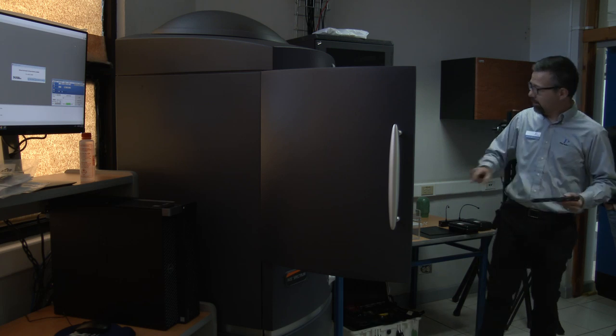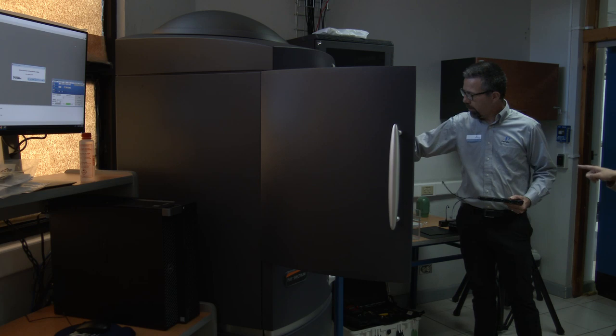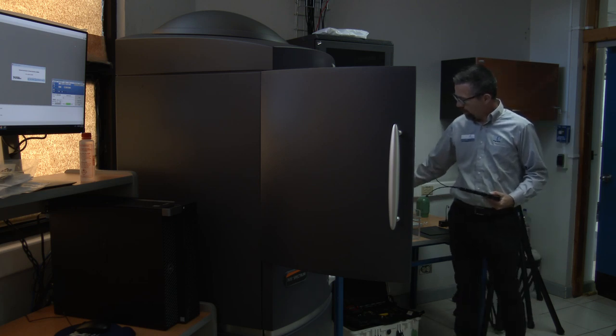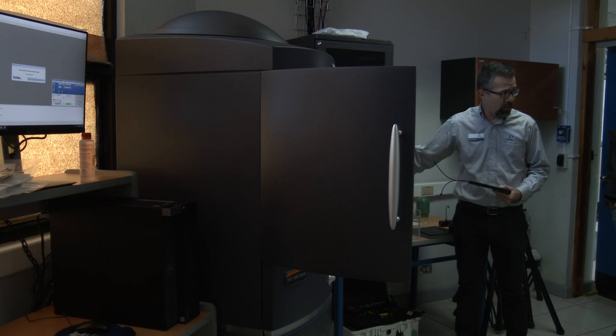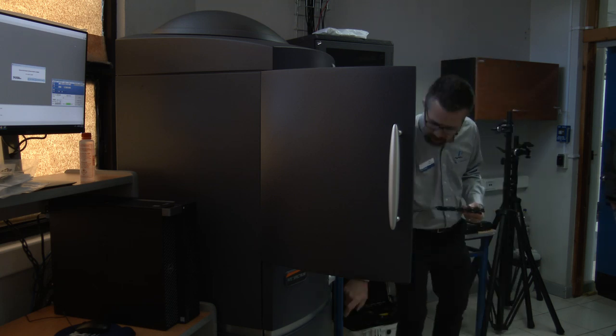It's going to get educted if we have this vacuum pump running. When we have the vacuum pump running, it's going to be pulling on this tube right here at a flow of 10 liters per minute. It's going to be pulling on the IVIS at a flow of 5 liters per minute. And there's one additional vacuum. It's way down in the bottom up here.